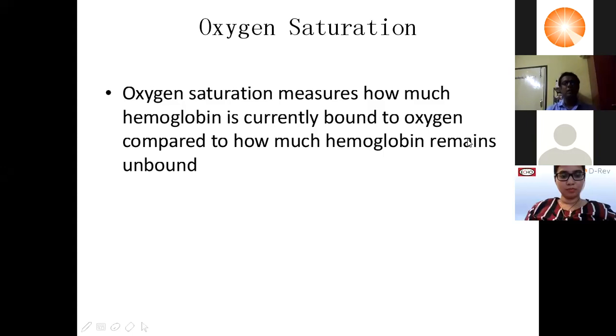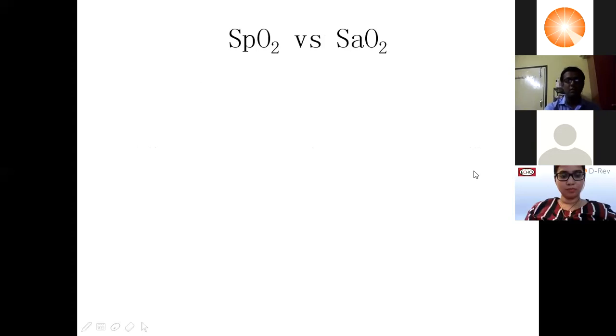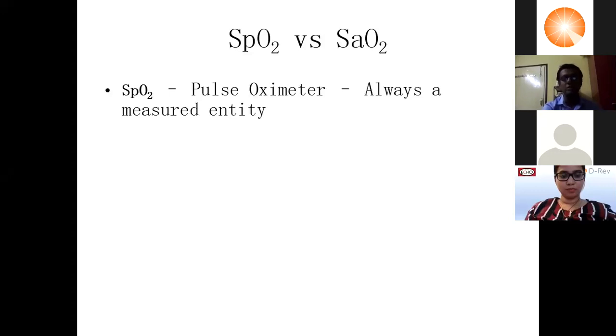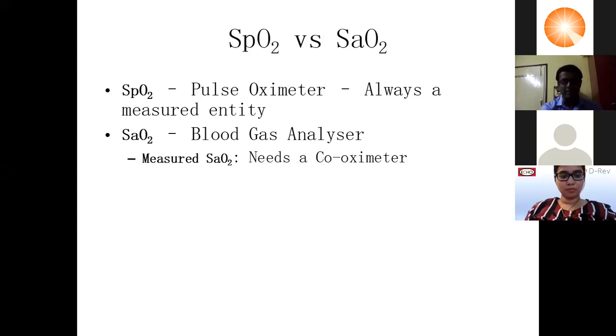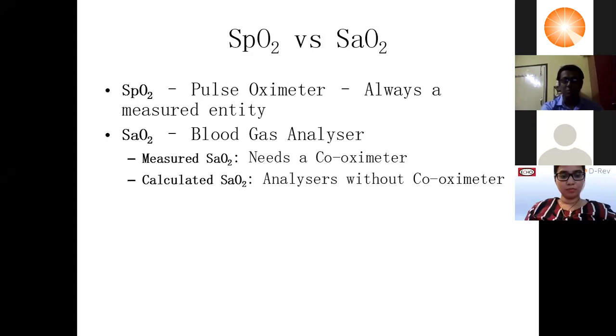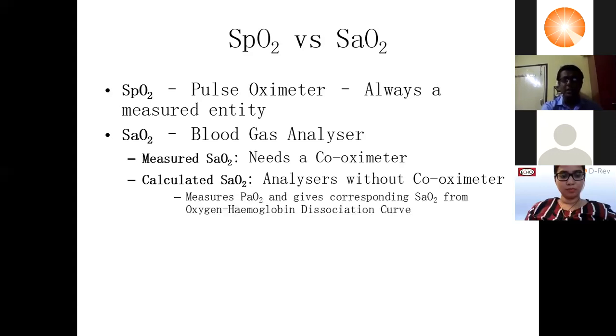Now, what does oxygen saturation mean? It is the ratio of hemoglobin currently bound to oxygen to the total hemoglobin level. There is another thing, SaO2, which is quite different from SpO2. SaO2 is an invasive measurement, while SpO2 is done by pulse oximetry. SaO2 is done by blood gas analyzer. The normal blood gas analyzers we use in our ICUs usually don't measure it; they just calculate it with the help of the oxygen hemoglobin dissociation curve. They put in the PaO2 and find the corresponding saturation from that.